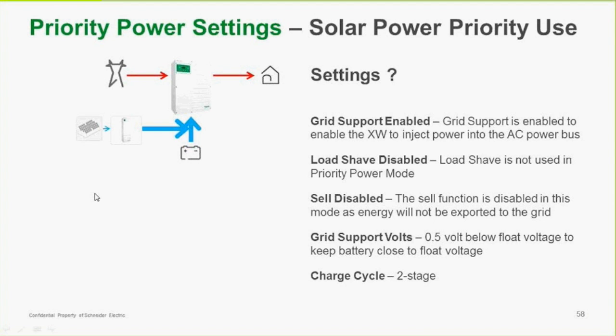So priority power settings is solar priority power use. These are the things that need to be adjusted when you're using priority power settings. Grid support is enabled, load shave is disabled, sell is disabled, and the grid support volts are set 0.5 volt below float voltage to keep the battery close to float.